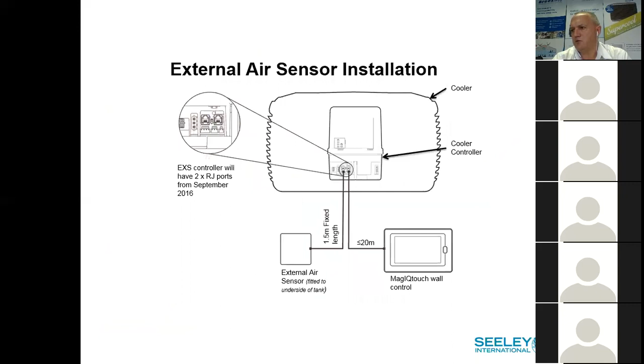Okay, just to discuss very quickly configuring up. One of the things I found is where in the multiple cooler situation before where we power up, say 10 coolers. So before powering up, ensure all appliances and components are connected to the network. Where there's only one of each appliance type fitted to the system, ensure all appliances and components are powered. Where there are 2 or more appliances of the same type connected, ensure only the first one is powered up. So an appliance is either a heater or a cooler. A component is an air sensor, zone board, or slave controller.